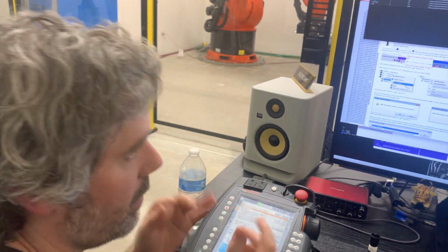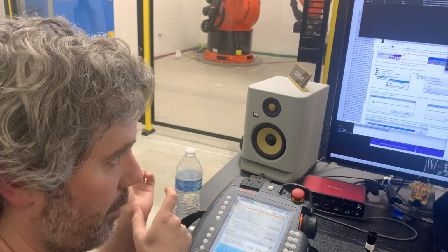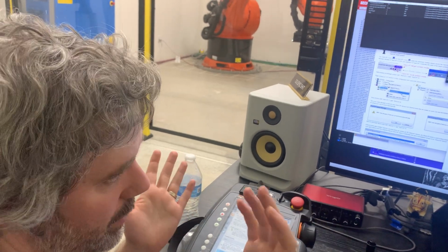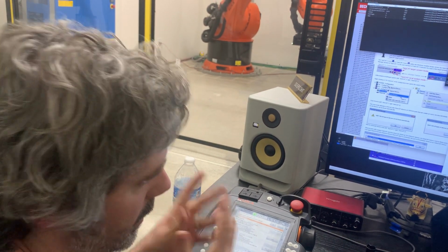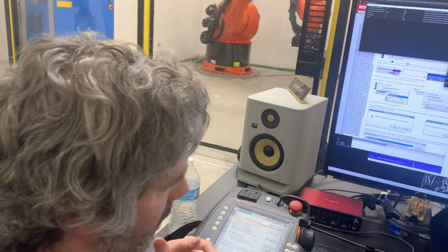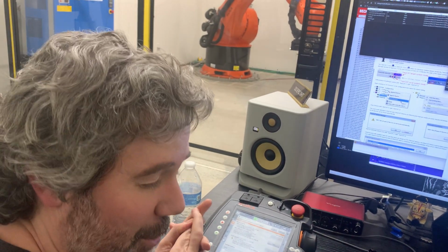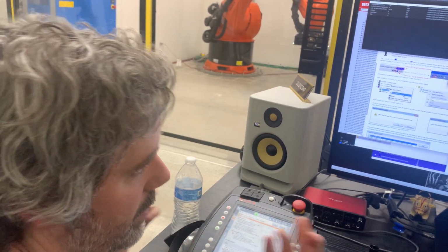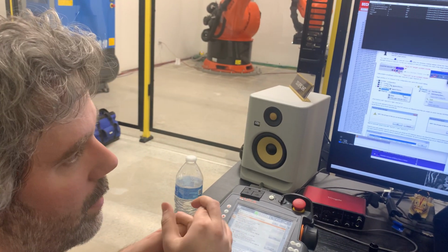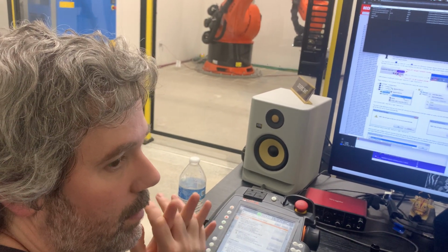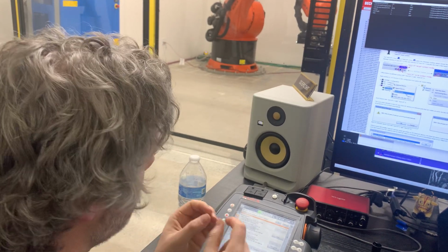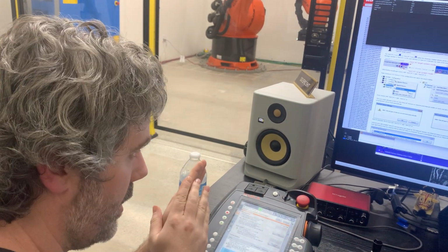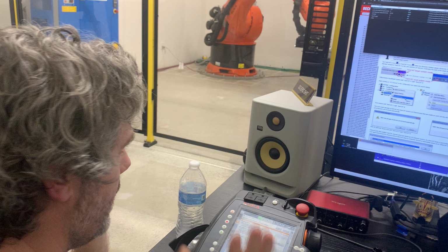Log in without any change is for when you think you made a mistake but want to view something. If your code is similar enough, you can then view things, but in general you shouldn't. Log in without any change sometimes won't let you log in, but sometimes it will, and it'll let you view the code that's on there and look at state. Log in with online change is an attempt to not stop the PLC and load the changes. Log in with download is download the entire new project.